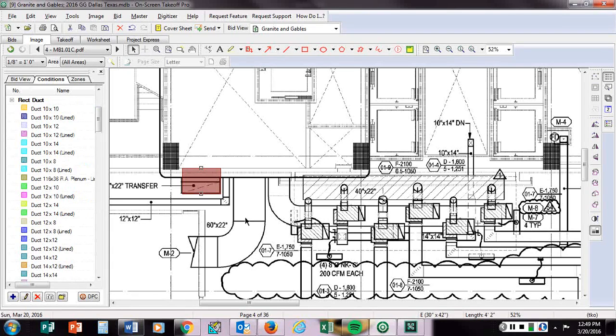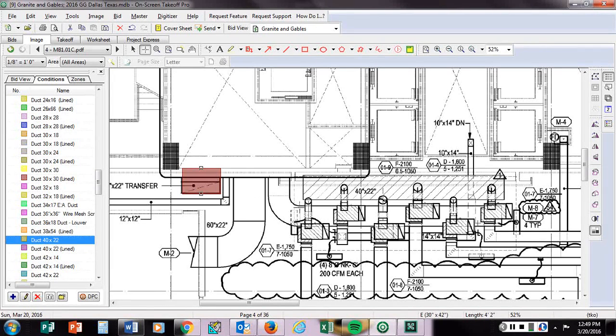If I were to look at this, that's 40 by 22 duct, and that happens to be insulated but not lined duct. So if I did 40 by 22 duct here, I could come across - and you can see it really doesn't fit real well there, but I took that duct off. Now if I go to pointer mode, spacebar, and grab this, you'll see how that fits real well in this other duct down below here. So what's going on is this ductwork doesn't actually run here, it runs down here.